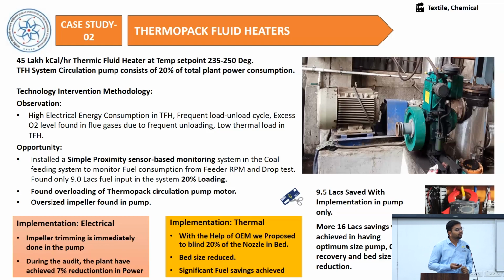We observed that the thermic fluid system the OEM suggested to the industry is very oversized. Now they have purchased the whole system, installed all the instrumentation and the necessary pumping system for the thermic fluid, and they cannot change the entire system. We helped the industry by showing how they can retrofit the existing system to achieve optimum power consumption. First we did the impeller trimming of that pump, because the rated power of that pump is 37 kilowatt and it was consuming 50 kilowatt. It was a totally oversized pump, and the OEM supplied a wrong size of impeller in that pump. So we identified that opportunity and trimmed the pump.